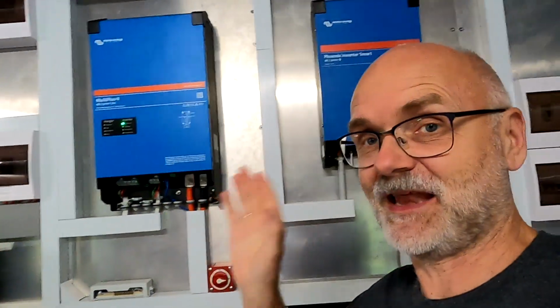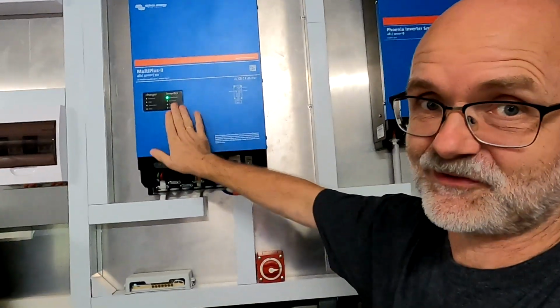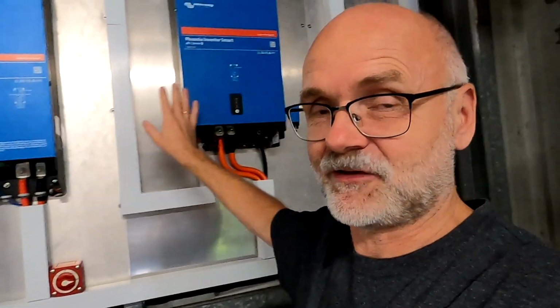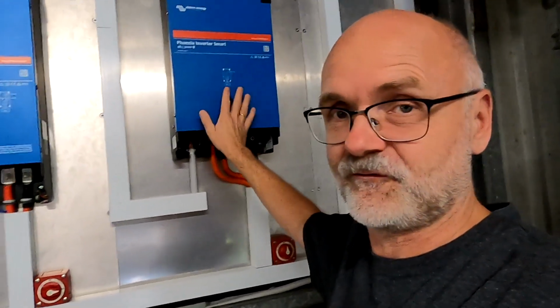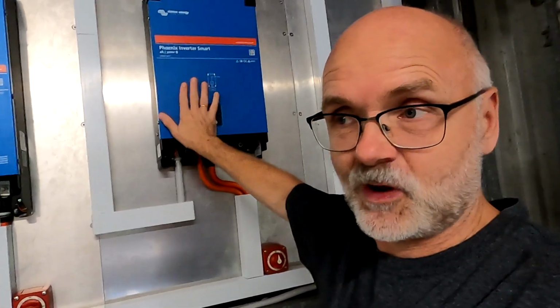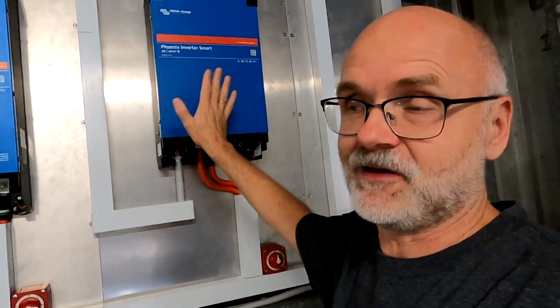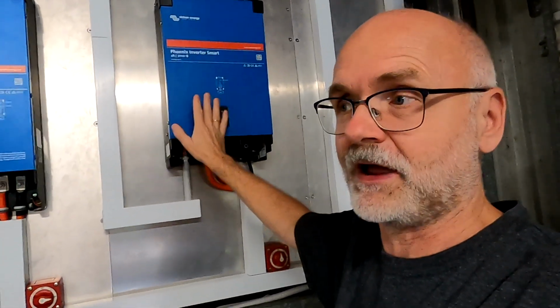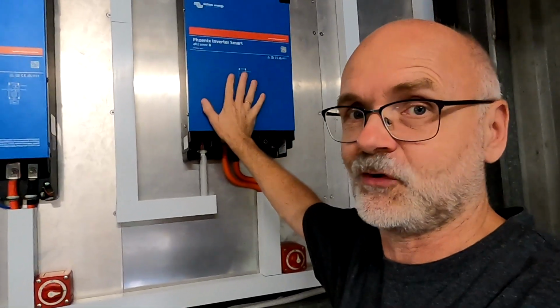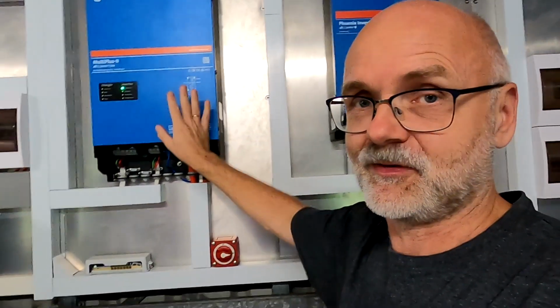The alternative setup could be: we have the Multiplus running all the time, delivering power up to 4.7 kilowatts to our load. If more load is needed, it automatically turns on the Phoenix. So most of the time this one stays off, and only if additional power is required does it automatically turn on, started by the Multiplus.